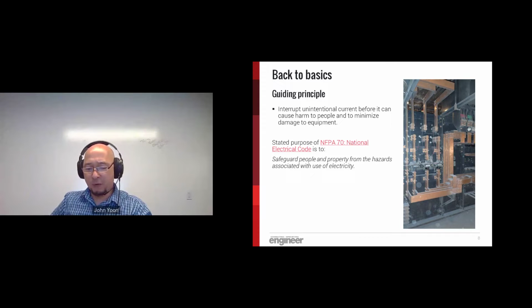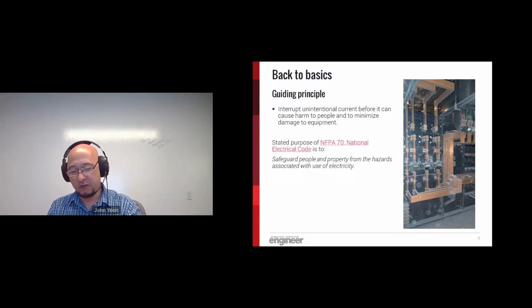For this webinar, we're starting out with an excerpt directly from Article 90, the Introduction to the National Electrical Code. The stated purpose of the code is to safeguard people and property from the hazards associated with the use of electricity. So when we design electrical distribution systems, the typical focus is on ensuring that the equipment and wiring methods that we specify have appropriate capacity and configuration to reliably serve whatever loads may be connected to that system. However, what we often lose sight of is the fact that there are inherent hazards associated with the use of electricity. Ultimately, when we design electrical distribution systems, we need to be able to interrupt the unintentional flow of electrical current before it can cause harm to people or damage equipment.